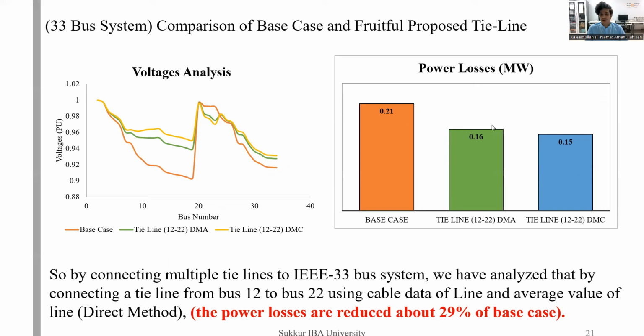So this is the power losses comparison. This is the base case where we have 0.21 megawatt losses. By connecting a tie line, we have reduced power losses from 0.21 to 0.16 megawatt. And by connecting a tie line from 12 to 22 using the direct method cable, we have reduced the system power losses from 0.21 megawatt to 0.15 megawatt.